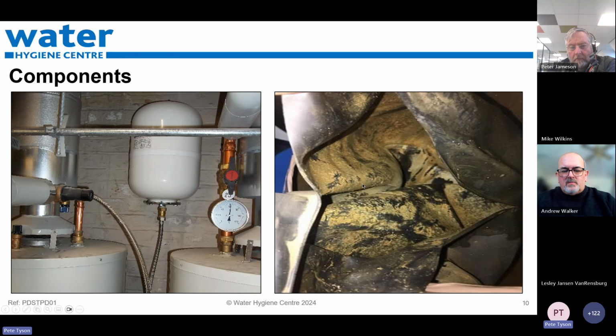And the new expansion vessels have changed design from these types, where there's a way in but no way out. We can put in what's called a flushing valve, which makes sure we've got flow going in and flow coming out, the new flow-through design. So we have water going in and water coming out, reconfigured into the system, so it's not wasting water.